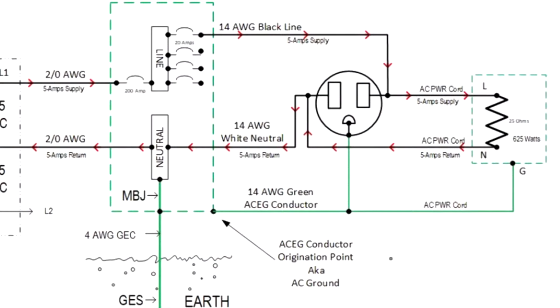And if you want to know what the number is, 2.5 volts is the maximum limit, and that would be at 15 amps. So what is ground doing? Well, it's pretty obvious. It's holding this chassis at 0-volt level. Also, if this were to use the ground as some sort of signal reference, it would also be our 0-volt reference. So that's pretty much how your home circuits work. It's really pretty simple. So let's take a look at the next slide and see what happens when a fault comes along.